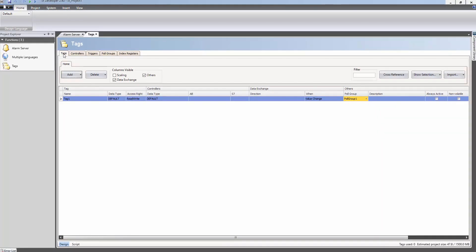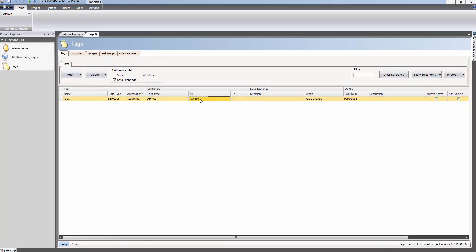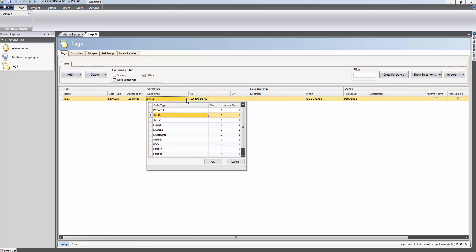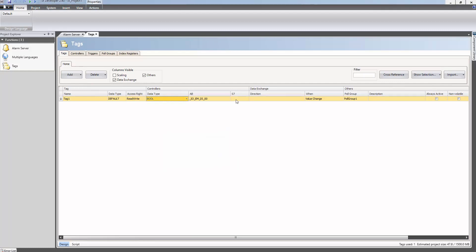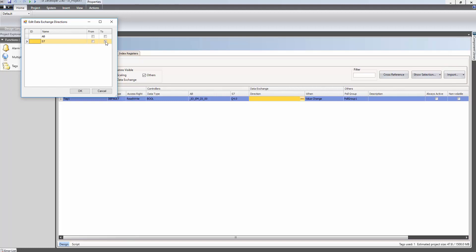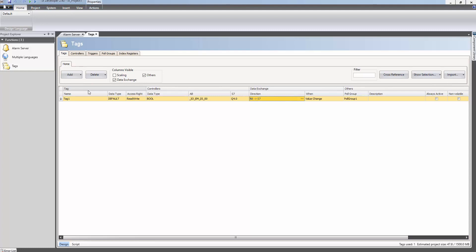The Tags tab is selected, and then the address that should be used in the Micro 800 controller is typed in. The data type is automatically changed to Boolean. Finally, the address that should be used in the Siemens system is added to the S7 column. In the Direction column, a dialog appears allowing you to select how the data should be exchanged — in this case, the data will be moved from the Micro 800 to the Siemens controller.